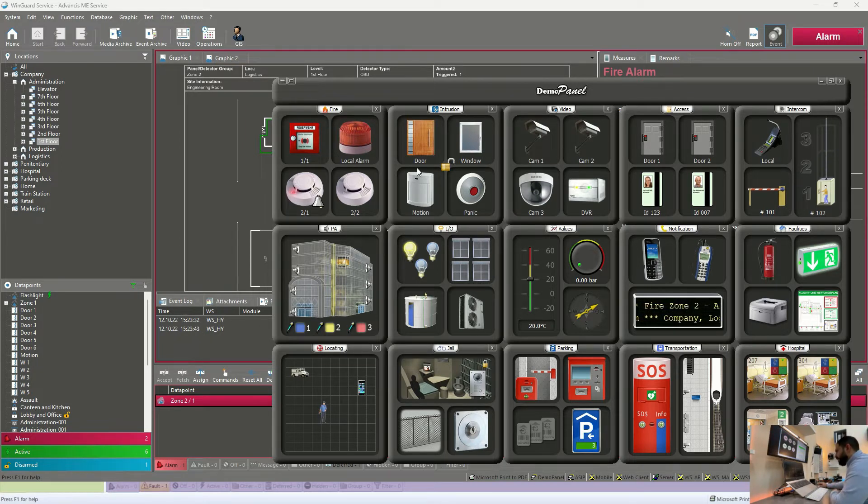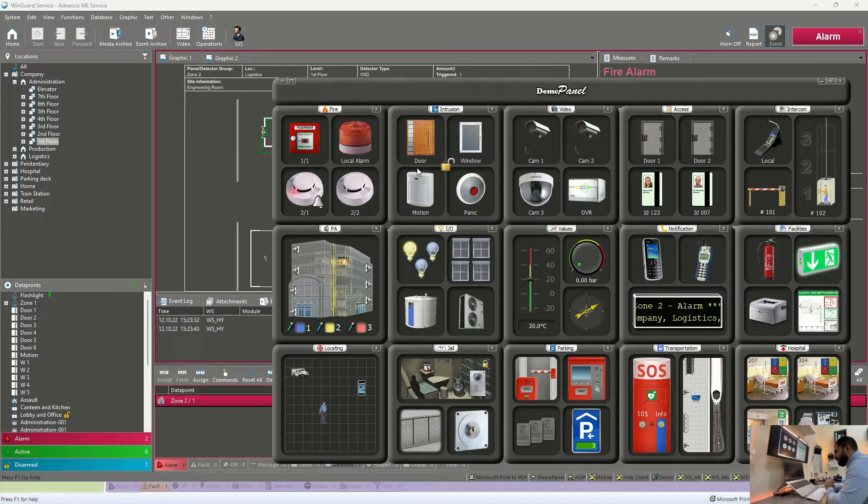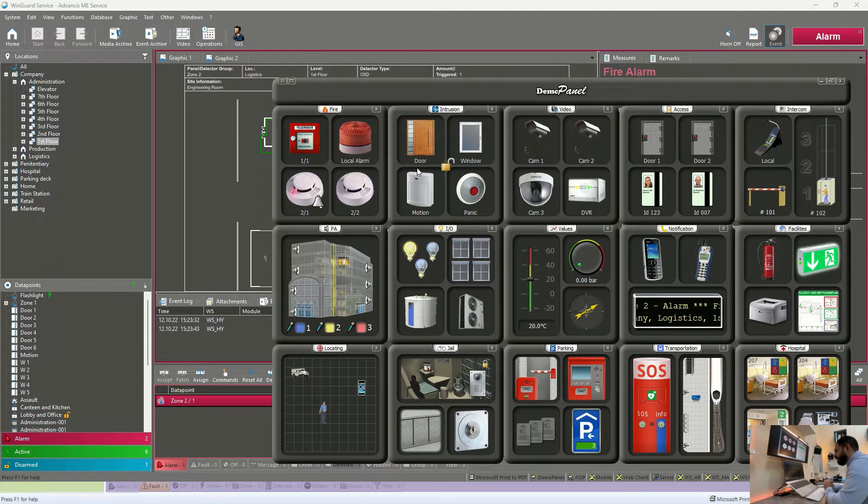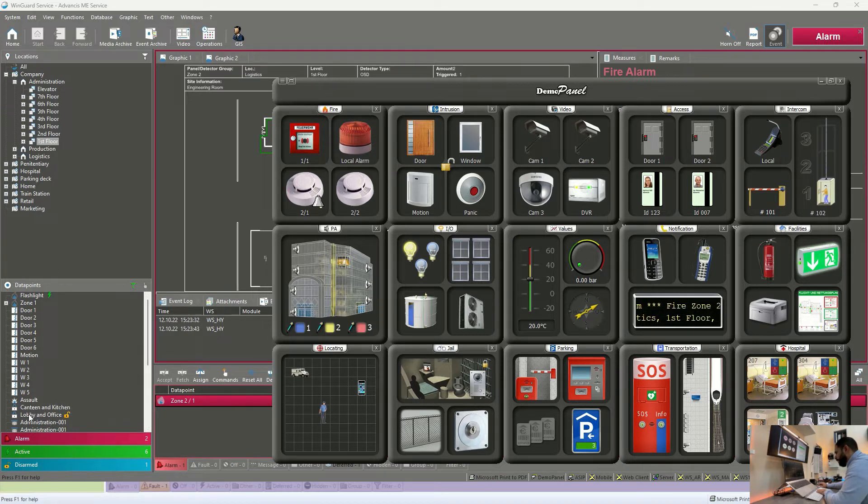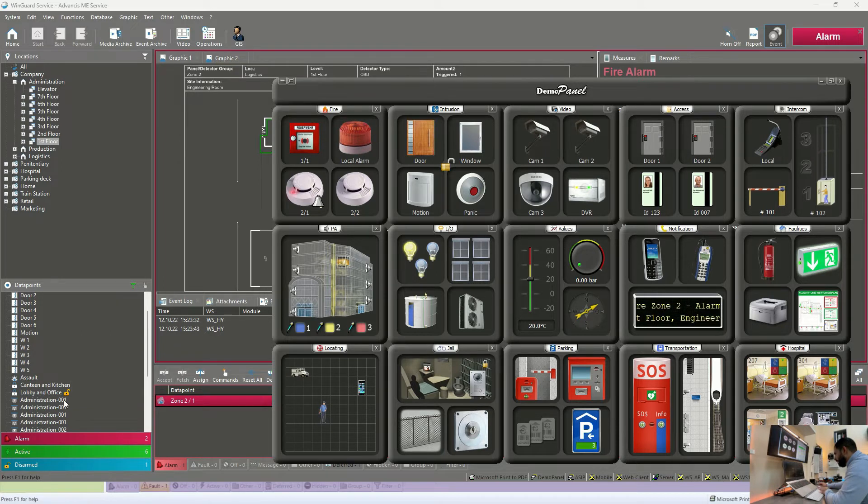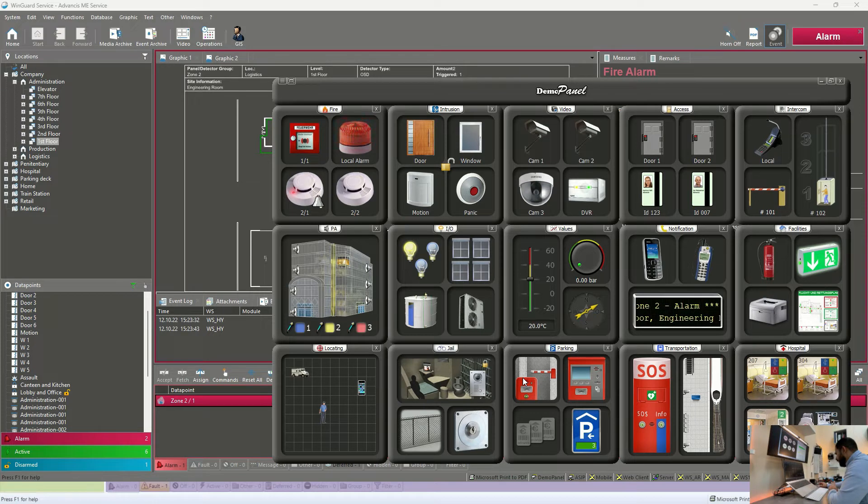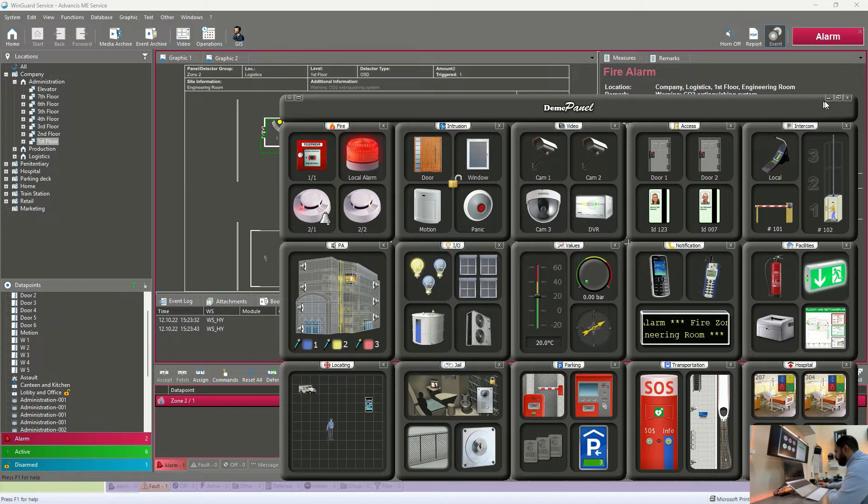Some motion detection and some points related to intrusion detection system were automatically disarmed to prevent any false alarm coming to WinGuard during the evacuation process. We have also automatically some doors were opened. You can see on the left side here, lobby and office, we can see this icon here that it is unlocked. So all of these actions are automatically done by WinGuard once we receive this alarm before even the operator do anything.